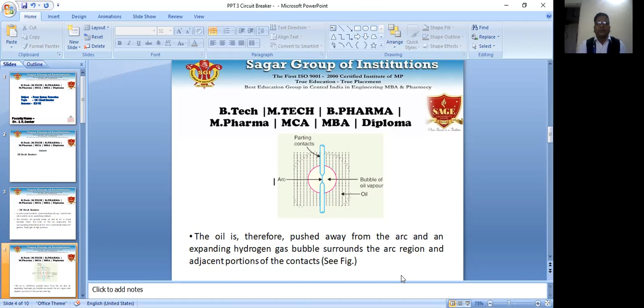The arc extinction is facilitated mainly by two processes. First, the hydrogen gas has high heat conductivity and cools the arc, thus aiding the deionization of the medium between the contacts. And secondly, the gas sets up turbulence in the oil and forces it into the space between the contacts, thus eliminating the arcing products from the arc path. So here the result is that the arc is extinguished and the circuit current interrupted.